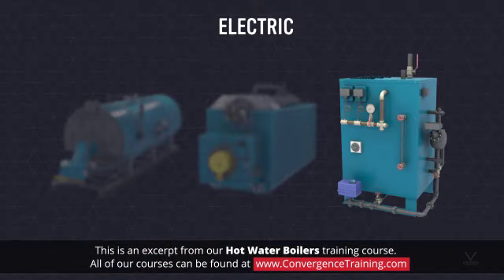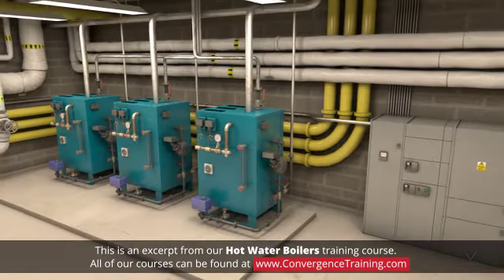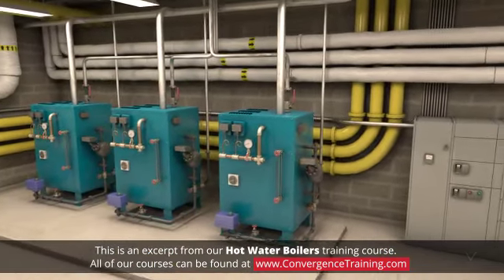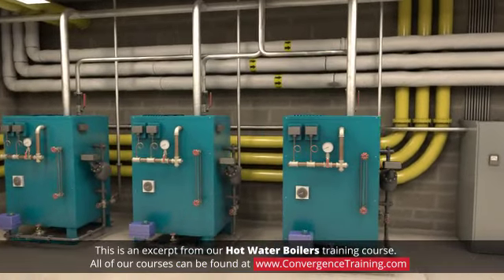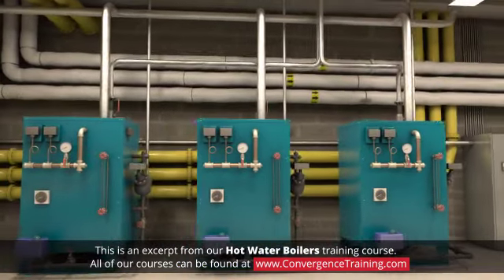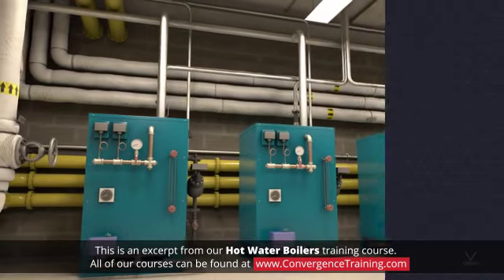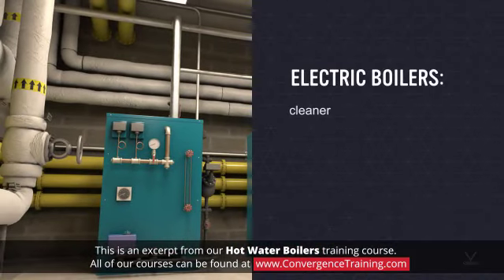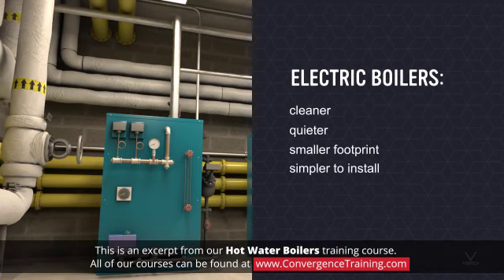Electric hot water boilers use electric resistance to generate hot water. Larger units used for hydronic heating of commercial buildings typically require three-phase power. Because they do not involve combustion, electric boilers are cleaner, quieter, have a smaller footprint, and are simpler to install than gas-fired or oil-fired boilers. However, they are usually more expensive to operate.